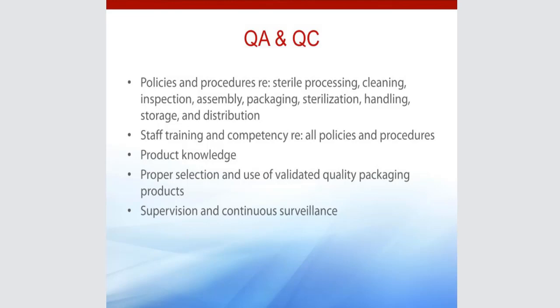You want to make sure that you're using the right disposable products to go with the right packaging. You can use aluminum foil in a dry heat sterilizer, but you can't use it in a steam sterilizer. You can use regular paper in a steam sterilizer, but you can't put it in a dry heat sterilizer that goes to 420 degrees because it'll burn up. So make sure it's apples to apples.